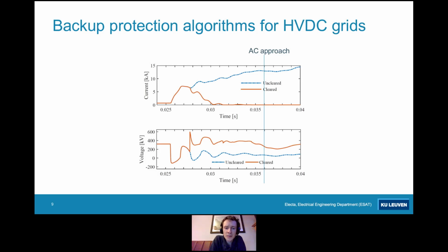Now in a DC grid, every millisecond is of importance because every millisecond the fault current is increasing. So it is of importance to detect breaker failure as soon as possible. And in my thesis, I have proposed an algorithm that can detect breaker failure even before the current through that breaker is zero. So the proposed algorithm has the advantage that you can react much quicker.